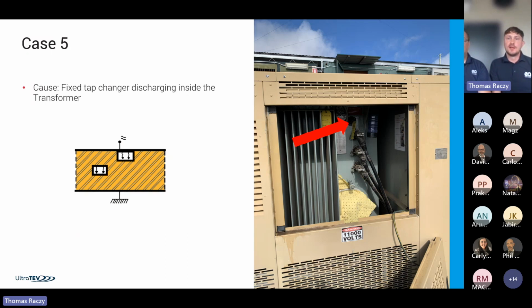After the initial testing of the transformer, there was a follow-up review of the DGA analysis, which is always a very good idea whenever you find any issues on oil-filled gear, to follow up with the DGA, and that indicated problems within the tap changer.